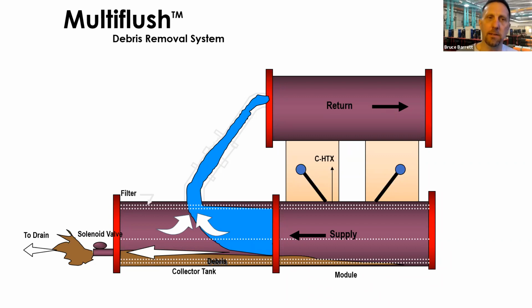Another item we've added is we call it a multi-flush. It's a debris removal system. We add an additional header on there. There's a solenoid valve that is controlled via our master controller, and every night it will dump some of that water, push the debris down to the end of the machine to keep it from fouling the entrance from the water pipes to the heat exchangers. So 2 added levels of protection, inline strainers and this multi-flush blowdown system that helps keep your heat exchangers clean. Again, still require an external strainer on these machines.